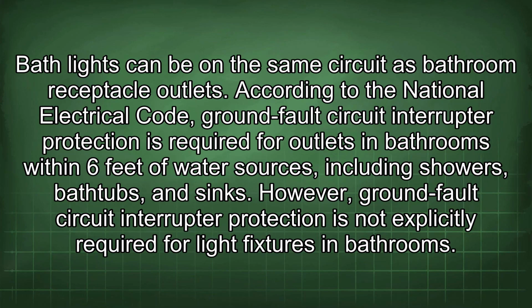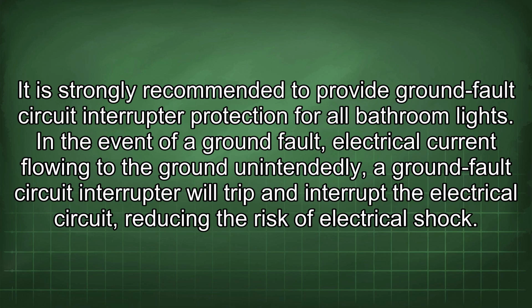Bath lights can be on the same circuit as bathroom receptacle outlets. According to the National Electrical Code, ground fault circuit interrupter protection is required for outlets in bathrooms within 6 feet of water sources, including showers, bathtubs, and sinks. However, ground fault circuit interrupter protection is not explicitly required for light fixtures in bathrooms. It is strongly recommended to provide ground fault circuit interrupter protection for all bathroom lights.